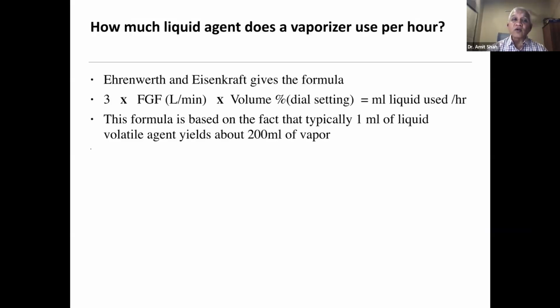Last slide. How to calculate the liquid agent the vaporizer uses per hour. This is calculated on the basis of the Ehrenwerth and Eisenkraft formula, which calculates 3 into the fresh gas flow which you use and the dial which you have set. Okay. So this will tell you the ml of liquid used per hour. Now this formula is based on one assumption that 1 ml of liquid typically forms around 200 ml of vapor. Okay. Now, halothane makes 229 ml, isoflurane makes 195 ml, sevoflurane makes 184 ml, and desflurane makes 210 ml. So generally, around 200 ml of vapor is made from 1 ml of liquid.